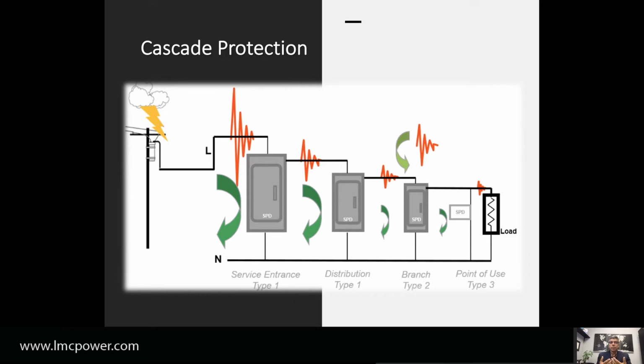But there are some people who will say, well, if I have a category C, that's all I need. Remember, I'm going to give you some of the reasons or excuses that people tell me. I just need an input surge protection. Okay, that will protect from anything coming in from the outside. But again, if you have a generator inside the building, if you have an air conditioner, if you have motors, if you have anything that is operating throughout the day, that will be generated on the inside of the building. That transient will not go all the way to the input of the building to go to ground. You need another surge protector within the building to be able to attenuate and deviate that energy to ground closer to where the problem is being generated, okay?